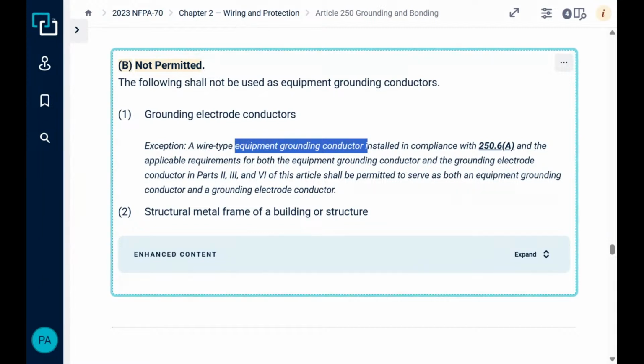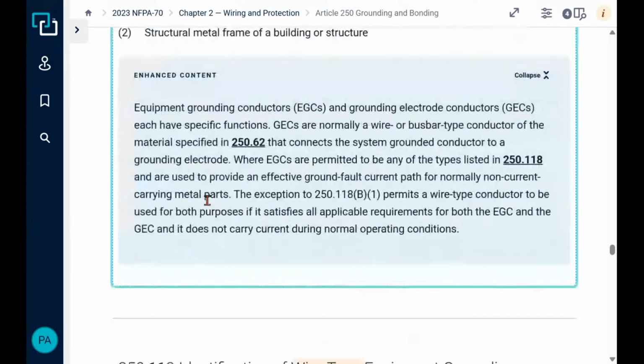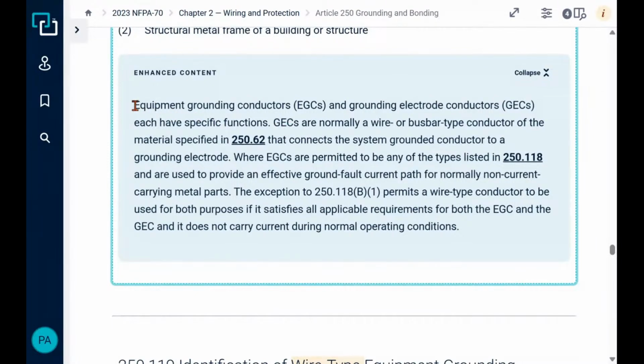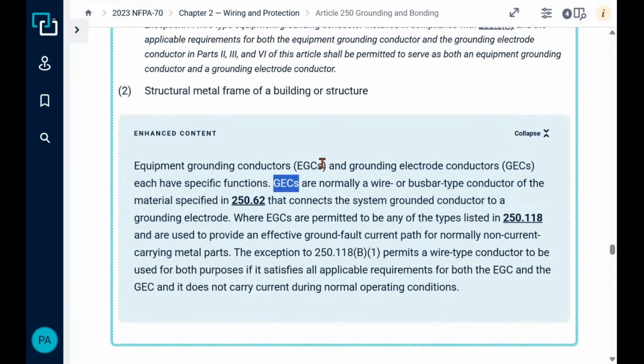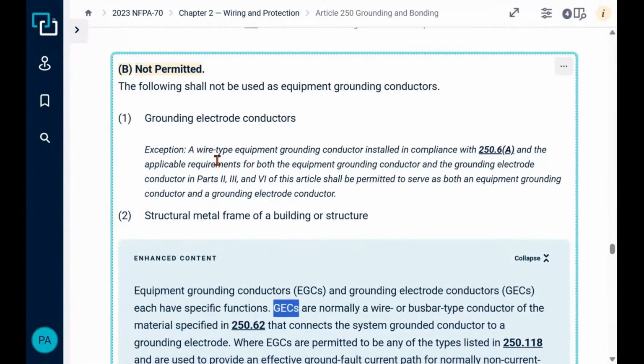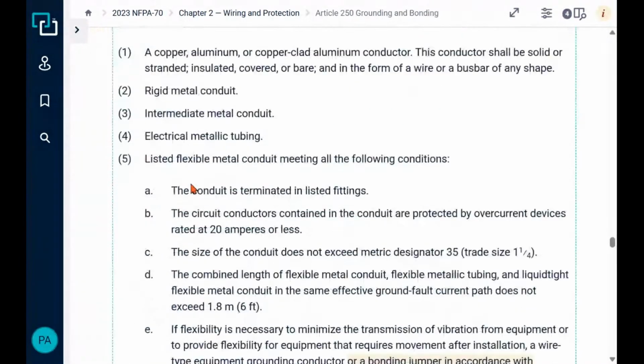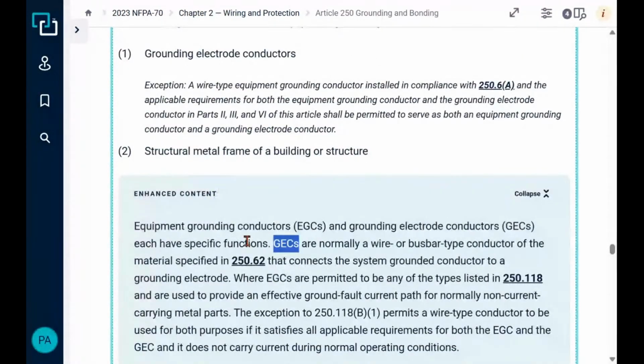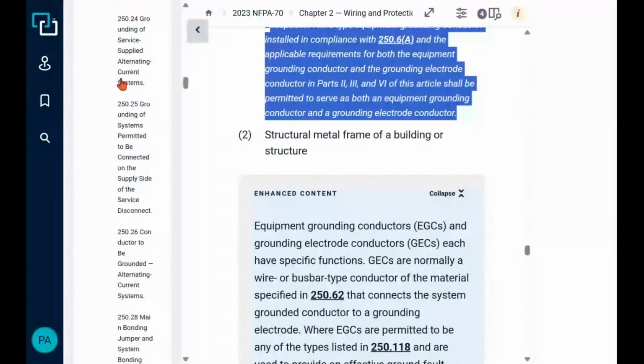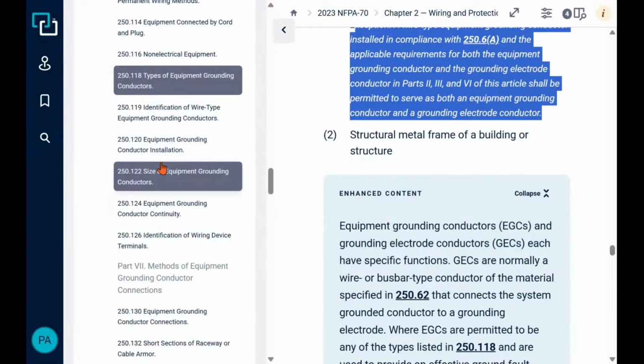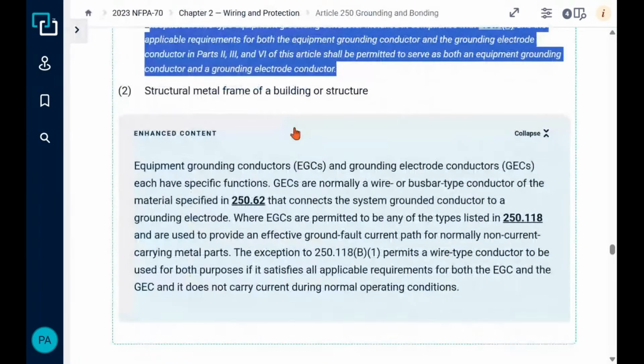So that EGC that might be running all the way to that remote distribution panel is being used as both, okay? That type of scenario. You have to still meet every bit of the rules. Now we can look here at the commentary, and this is what it's telling you right here in this commentary. It says, equipment grounding conductors, EGCs, and grounding electrode conductors, GECs, each has specific functions. Absolutely. Okay, the GEC is going from your neutral and it's connecting. It sounds like 250.121. That has moved, David. It is now under the exception here in 250.118. So the 121 has moved, right? And it is now down here for that, okay? Under right here. Because I'll show you, notice right here, David, we don't have a 121 anymore. It's gone, got moved. That's all it did, was drop it up in there, okay?